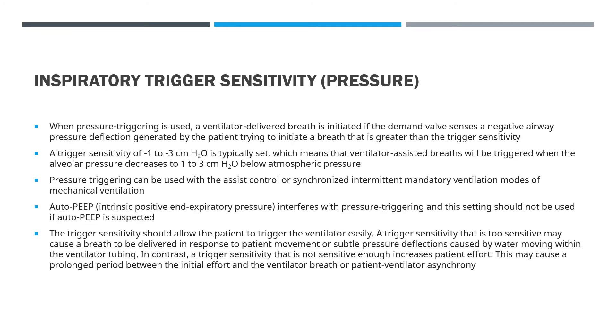In pressure triggering, the ventilator senses negative pressure in the circuit as a result of the patient's inspiratory effort. Trigger sensitivity that is too sensitive may cause a breath to be delivered even in response to the patient's movement or subtle pressure deflections caused by water movement within the ventilator tubing. If trigger sensitivity is not sensitive enough, it increases patient effort and may cause ventilator-patient dyssynchrony.